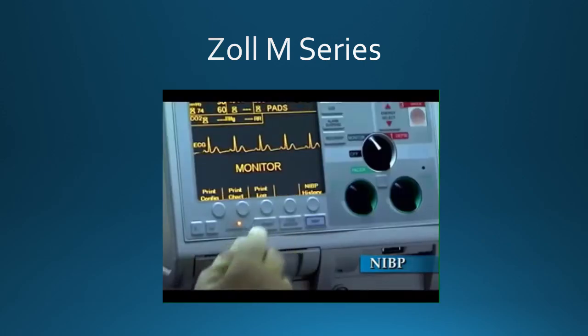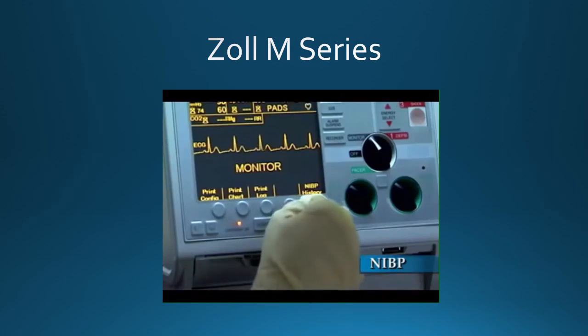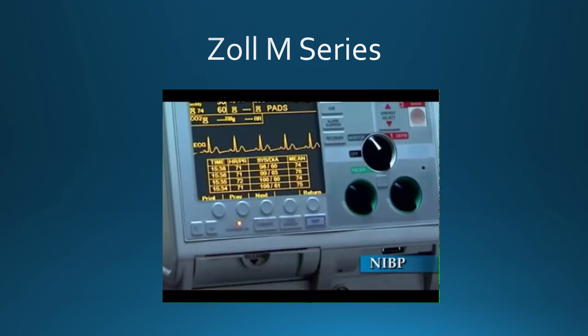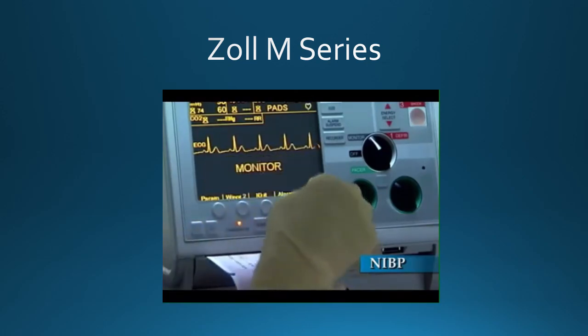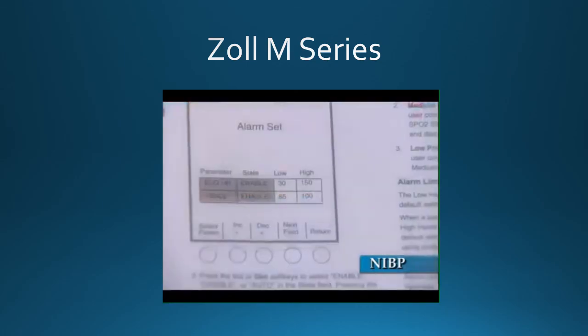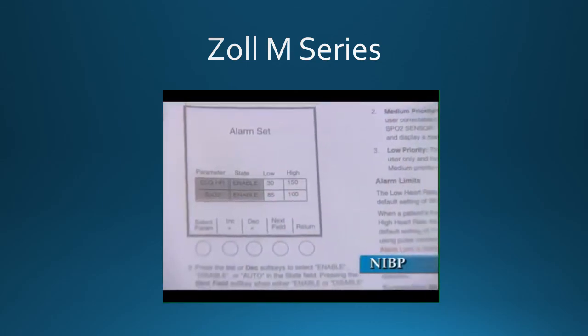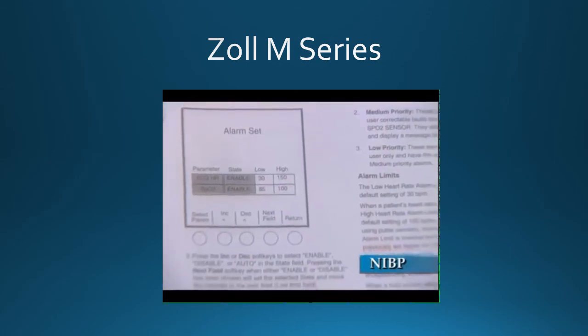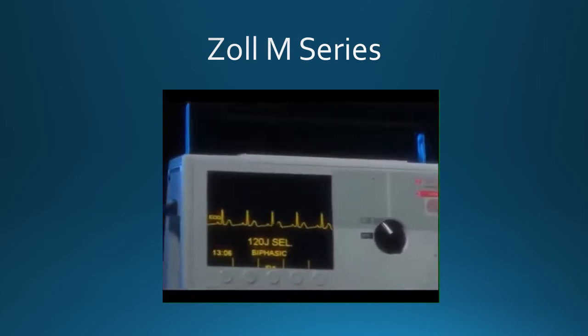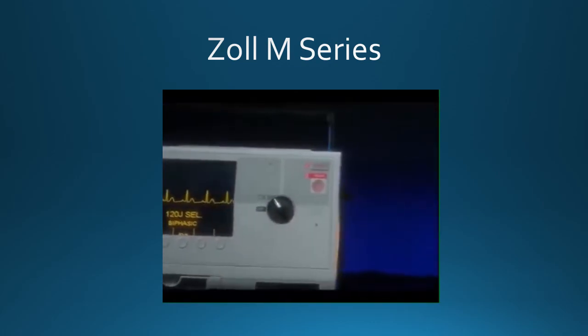By pressing the Summary key, then pressing the NIBP History soft key, the NIBP history will be displayed. Pressing the Print soft key will print NIBP, SpO2, and EtCO2 measurements if present. Pressing the Return soft key returns the user to the main menu. Please consult the M-Series Operator's Guide for detailed instructions on enabling and disabling alarms and how NIBP operates in the M-Series.